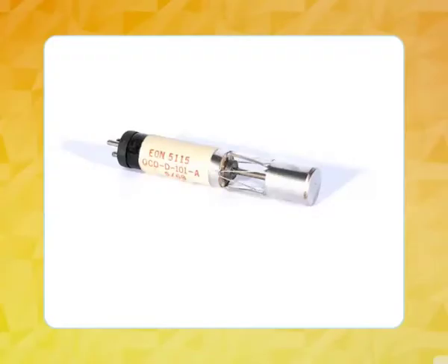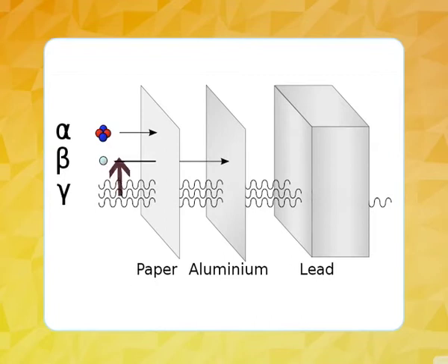Second is beta particles. Some beta particles can also be detected by a thin-walled windowless GM tube, which has no end window but allows high-energy beta particles to pass through the tube walls. Although the tube walls have a greater stopping power than a thin end window, they still allow these more energetic particles to reach the fill gas.